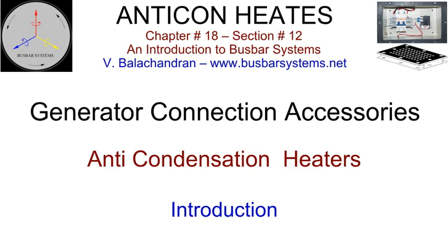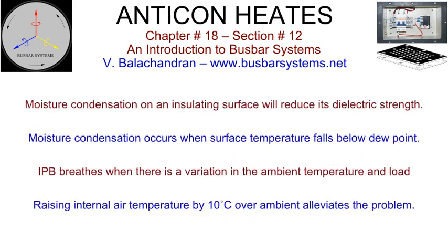Introduction. Isolated phase bus, which are not pressurized, need to be provided with anti-condensation heaters to prevent moisture condensation on the surface of the insulators and bushings. Moisture condensation on an insulating surface will reduce its dielectric strength. The moisture condensation will take place when the surface temperature of the insulator or bushing falls below the dew point.